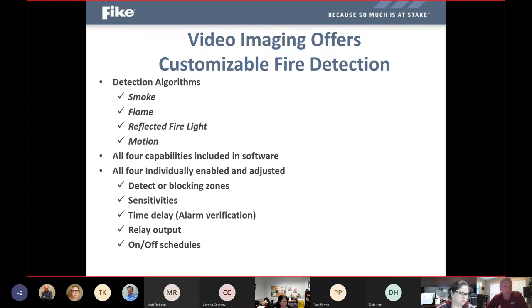But you can apply that same logic, based on exactly what the camera is seeing over the course of normal business occurring in that area, to know when you want to really focus on smoke or rule out smoke, if smoke and or steam is part of the normal operation in that camera's field of view. We don't want to detect on it when that's part of the normal operation during certain hours or days or parts of the shift, but we can respond to it at other times, just based on how we're going to program everything. So very customizable.